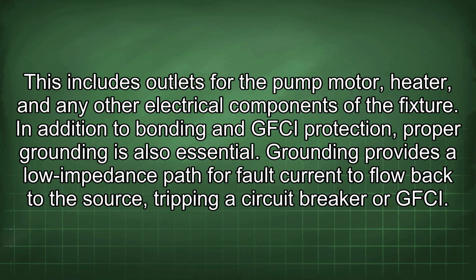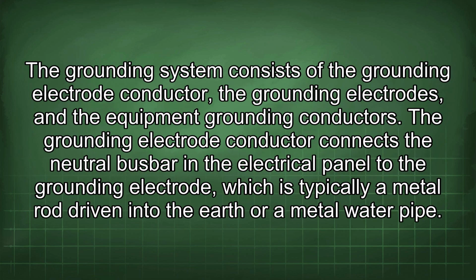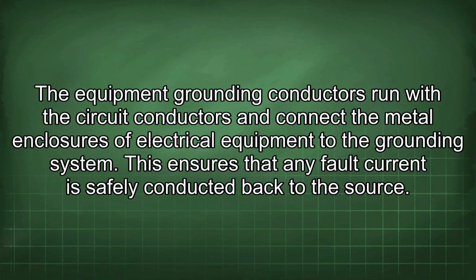In addition to bonding and GFCI protection, proper grounding is also essential. Grounding provides a low impedance path for fault current to flow back to the source, tripping a circuit breaker or GFCI. The grounding system consists of the grounding electrode conductor, the grounding electrodes, and the equipment grounding conductors. The grounding electrode conductor connects the neutral busbar in the electrical panel to the grounding electrode, which is typically a metal rod driven into the earth or a metal water pipe. The equipment grounding conductors run with the circuit conductors and connect the metal enclosures of electrical equipment to the grounding system. This ensures that any fault current is safely conducted back to the source.